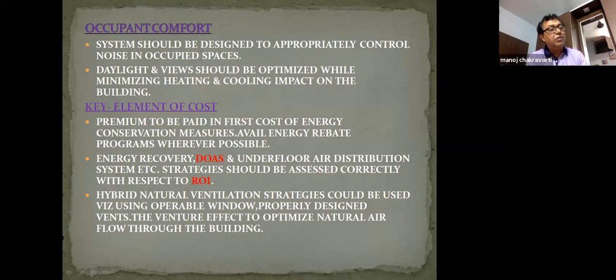Energy recovery and underfloor air distribution systems give a lot of minimization in consumption, because normally in an office the cooling requirement comes up to about 6 feet level; above that, cooling is not needed. Normally when we throw the air from the side or top, we throw it above 10 feet level, so it comes down from 10 feet to 6 feet and below.